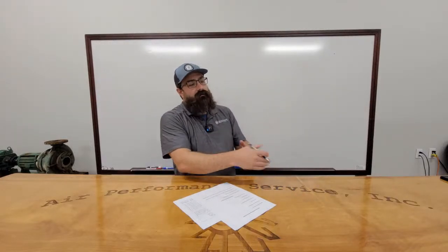I wouldn't know. I would say return side, but that's typical of most valves. Most valves you're going to put on the return side. That way you don't starve an evaporator, or not an evaporator, but starve a coil. If it's in front of the coil, it can technically pull out and create dead space in the coil, and you may get a pocket or something in there. But if it's always got water in the coil, that can't happen.